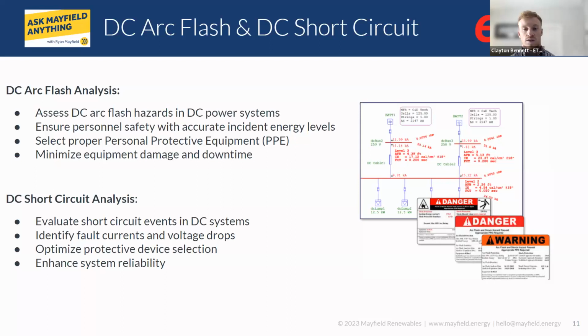As I mentioned, the DC arc flash and short circuit modules are integrated within the one line, and probably the most optimal way of utilizing the DC arc flash application is with our arc flash result analyzer. That's something that's accessible when running a study. You look at it in a tabular view and you can add any sort of report you'd like to the analyzer. And this helps you evaluate, really for us in the concern of safety and protection of our equipment, worst case incident energy levels. With ETAP, you can use this result analyzer to set up marginal and critical alerts throughout your DC network. And that's a really quick way of evaluating a DC system as it pertains to arc flash.